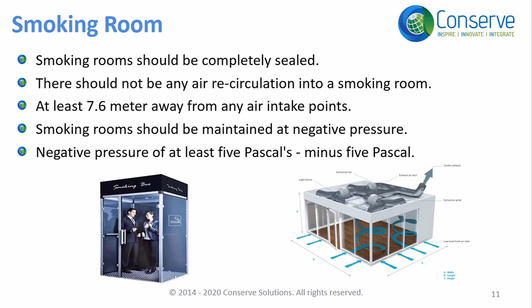The third requirement is the exhaust should be at least 7.6 meters away from any air intake points, so that it will not enter the building and contaminate the space. And finally, smoking room should be maintained at negative pressure. Negative pressure of at least 5 Pascal, that is minus 5 Pascal compared to adjacent spaces. The negative pressure will ensure that when the doors are open, air from the adjacent spaces will come into the smoking room and the contaminated air in the smoking room will not go into the adjacent spaces.